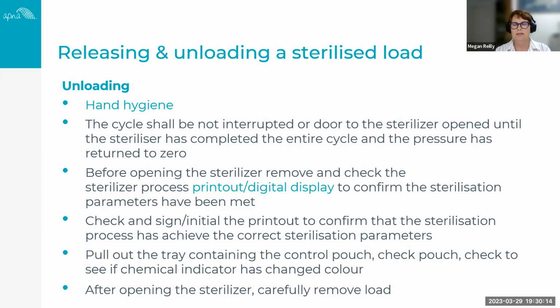I think that's the important thing about sterilizers, is they're a pressurized vessel, and you have to have your certificate in relation to that. So they're not a safe item necessarily, because they are pressurized. So sterilizers these days, you can't open the door or crack the door unless you've got a very old one. But before you open that sterilizer, remove and check the sterilizer process printout. So if you have a record, or look at the digital display to confirm that the sterilization parameters have been met. So you really need to be familiar with what those parameters are, what the temperature, time and pressure is for the cycle that you have put those items on.